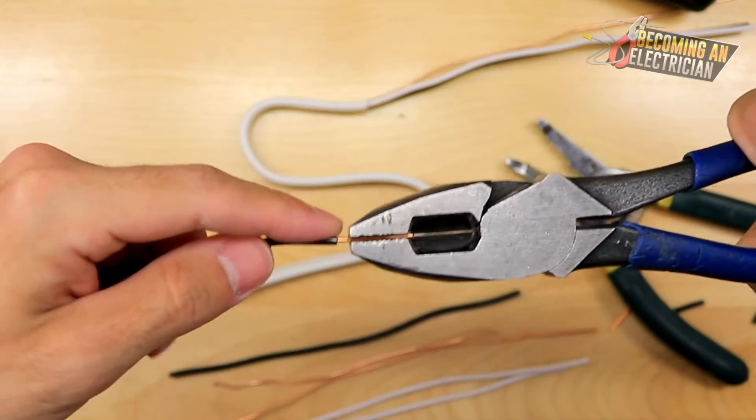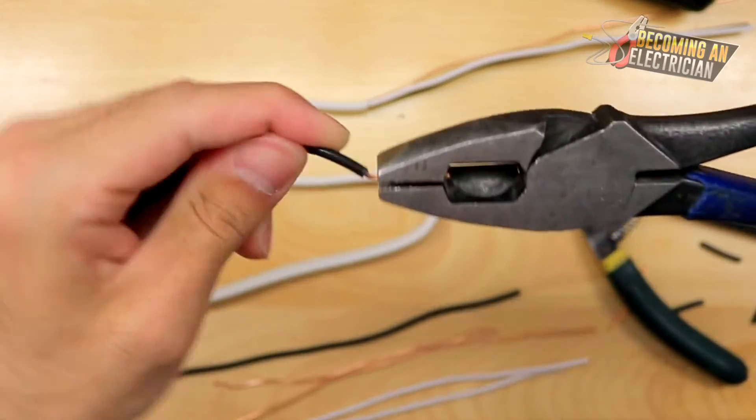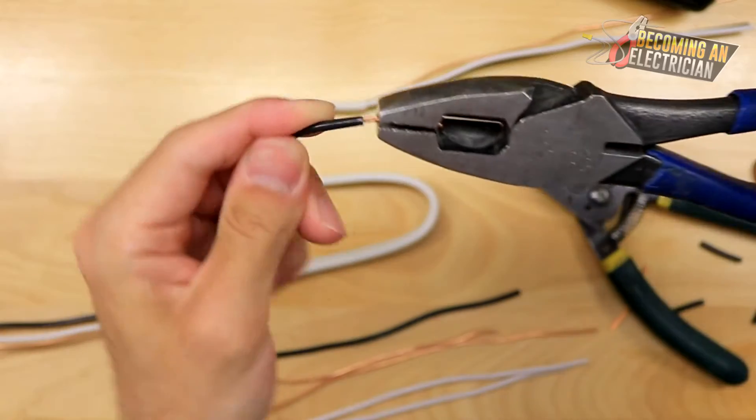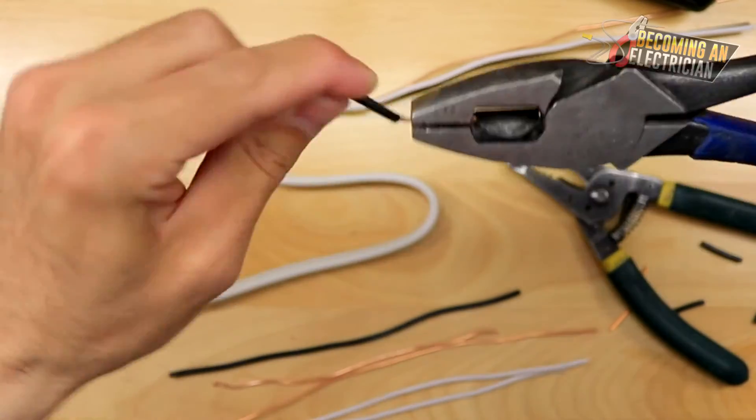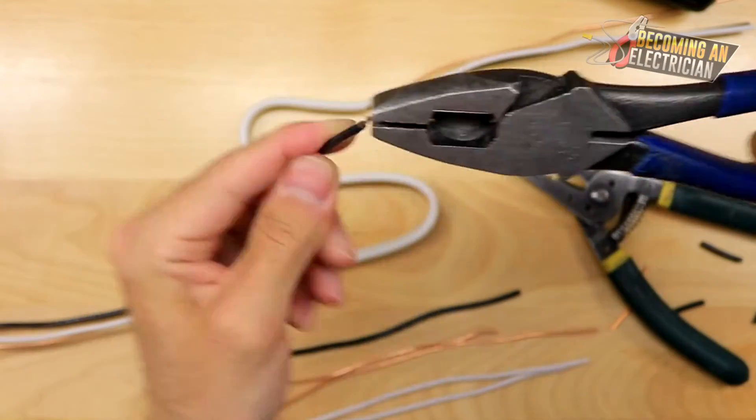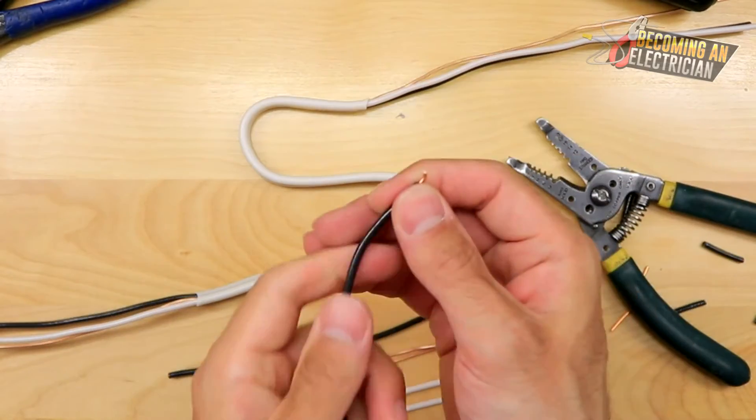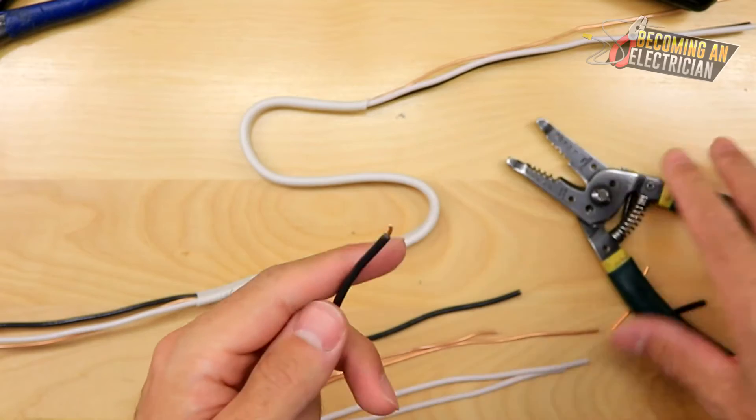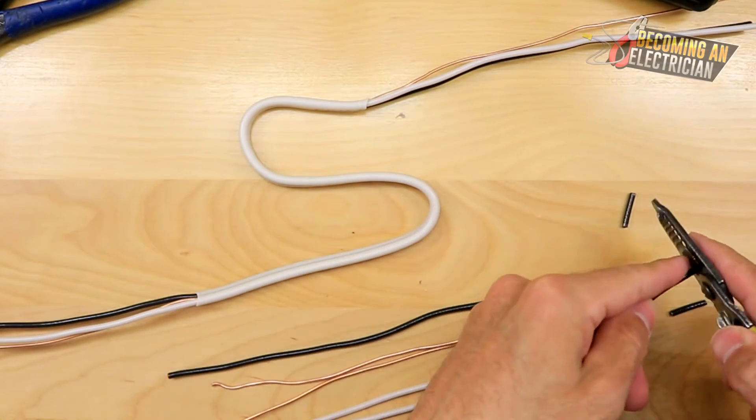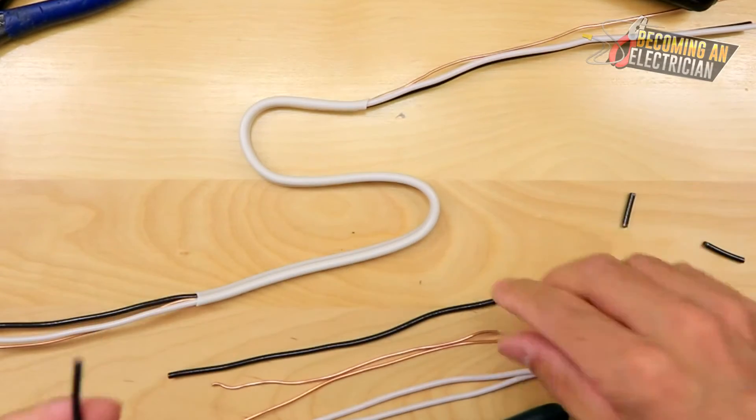Now again, this was a clean strip. I was not aggressive on it, and let's try to do the bend. Before it was nine. So one, two, three, four, and I'm being very aggressive. Five, six, seven, eight. So again, that's just showing you guys that if you don't score the wire, your wire is much stronger, and as an electrician, it's all about the integrity of the wire.